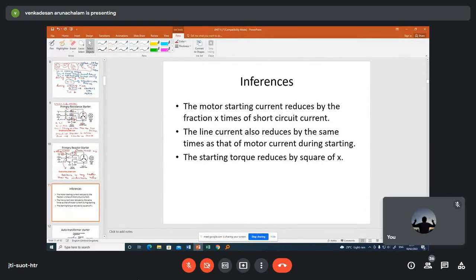If the starting torque reduces at one point of time, the motor refuses to start, because every motor should have a minimum starting torque. If it is not having any starting torque, then at one point of time the motor refuses to start at all. So the current is reducing, that is an advantage to us, but the starting torque is also reducing by the X squared term, that is a little demerit to us. But what is the advantage? Current reduction, that is overcoming the disadvantage. What is the disadvantage? Torque reduction.